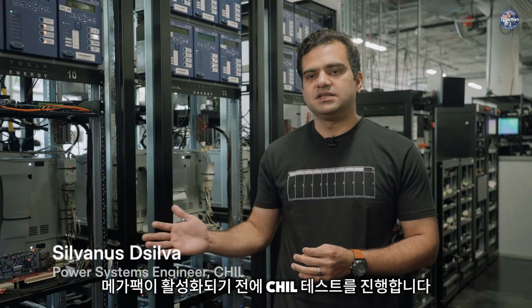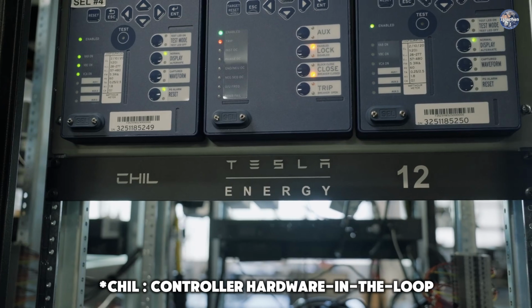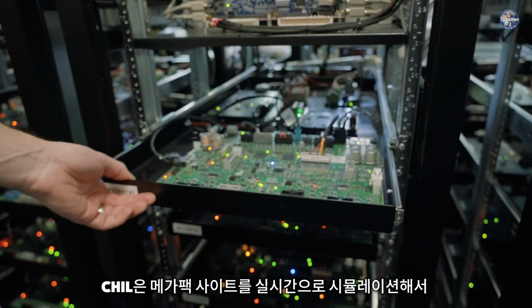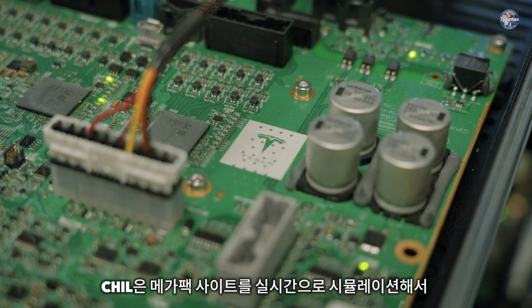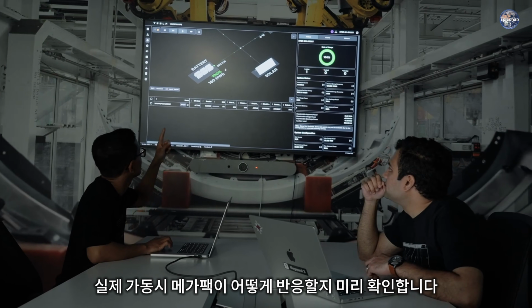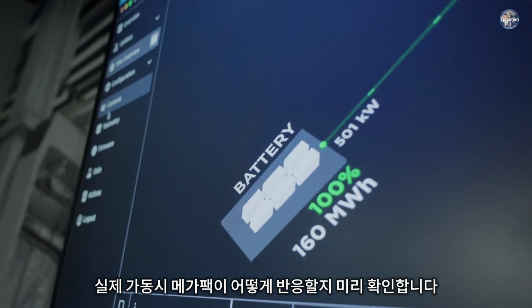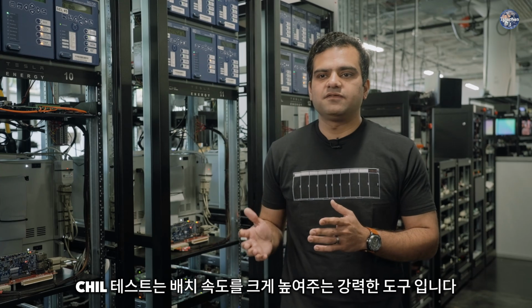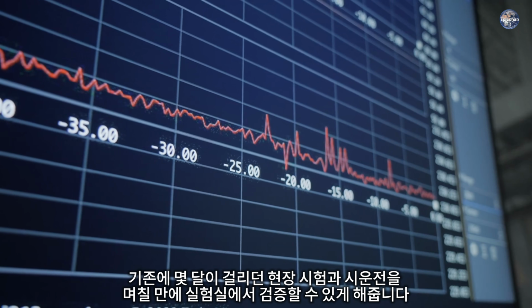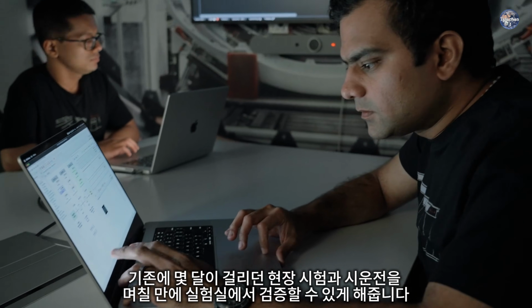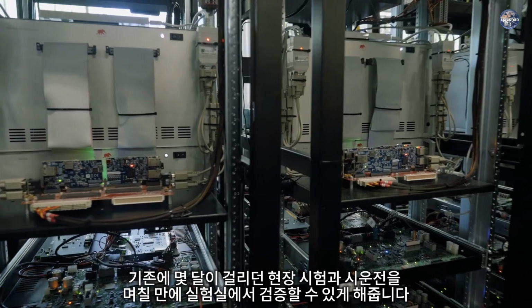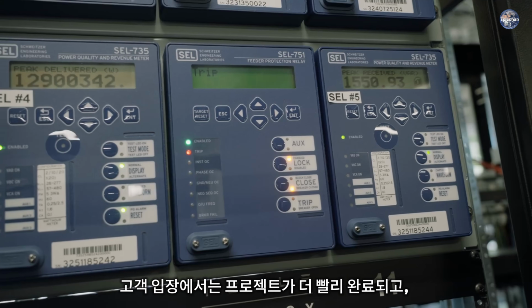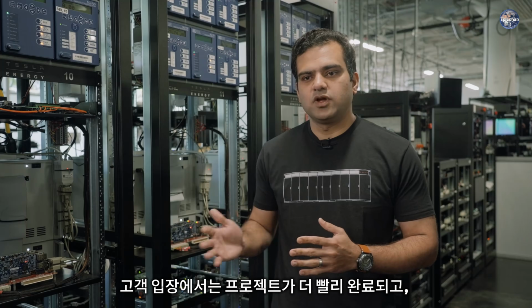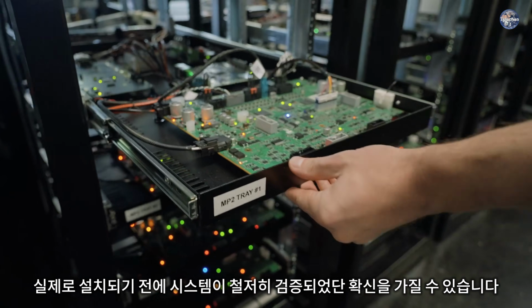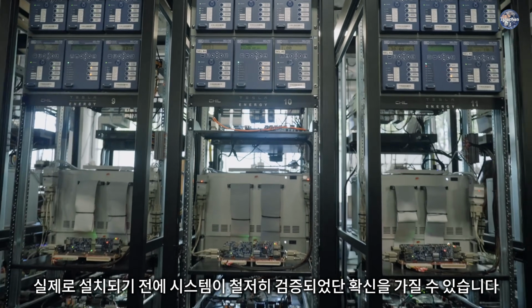Before the Megapacks are energized, they go through CHIL testing. CHIL stands for Controller Hardware in the Loop. CHIL helps us deliver a real-time simulation of the Megapack site to mimic how the Megapacks would respond once the site is fully operational. CHIL testing is a force multiplier for our deployment speed. It helps us compress what would traditionally be months of field testing and commissioning into days of lab validation. For our customers, it means faster project deployments, higher reliability from day one, and confidence that the Megapack system has been thoroughly tested before it is actually installed.